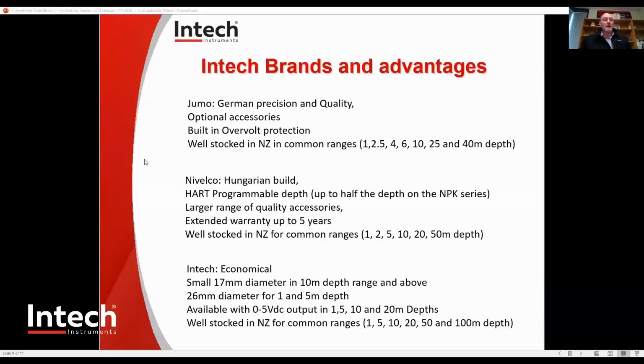Also, Nivelco has HART programmable models. So you can actually program the depth up to half of the depth, especially on the NPK series, not the NCK. They have a larger range of quality accessories, extended warranty up to 5 years, and we are well stocked in New Zealand at our stores for common ranges. You typically get 1 metre, 2 metre, 5 metre, 10 metre, 20 metre, and 50 metre depths.